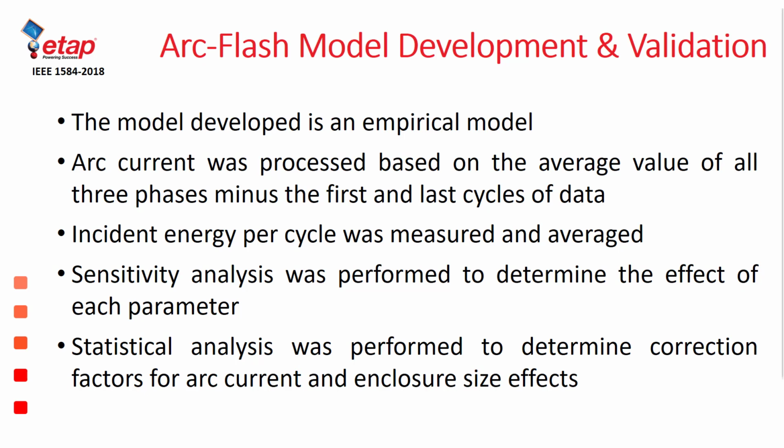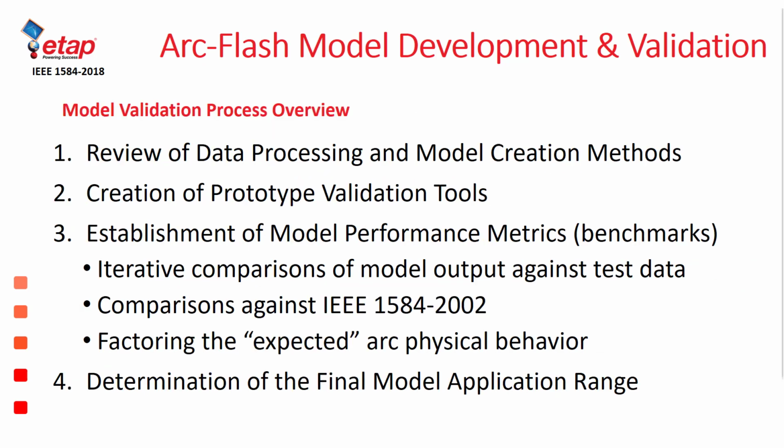We also have conditions which show no effect of the gap on the arc current for the majority of the model range on the current, and several other aspects of the old 2002 model which were all corrected in this model. So to summarize this slide, basically the new testing and the new model corrected a lot of the problems, and it is also not only based on the test results, but it's also based on the expected physical behavior of electrical arcs.